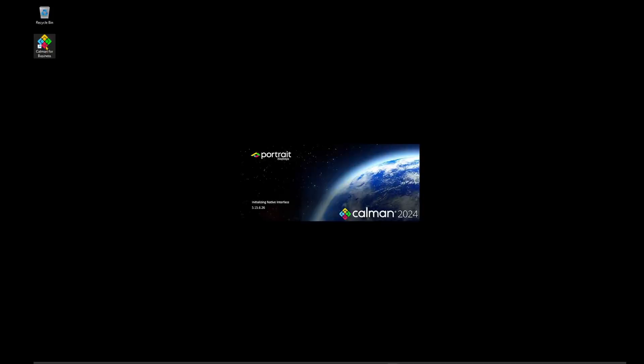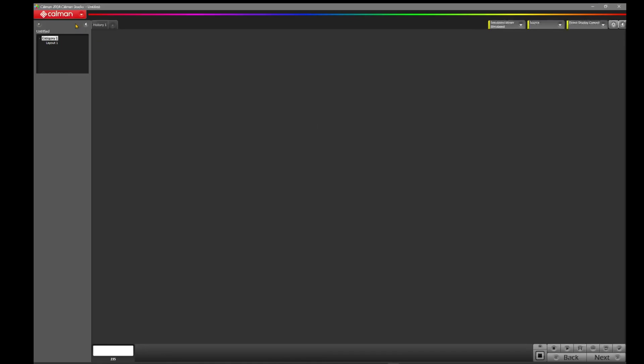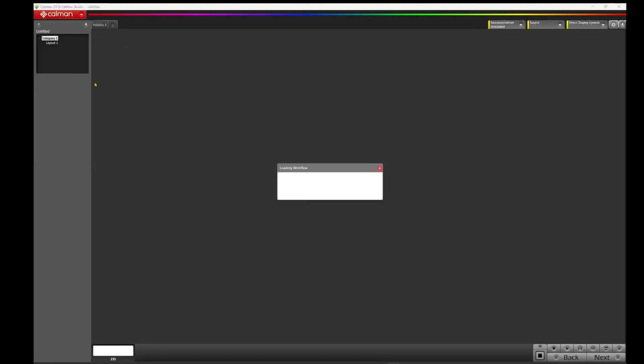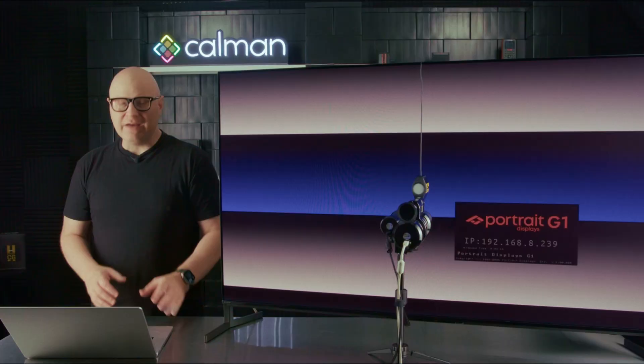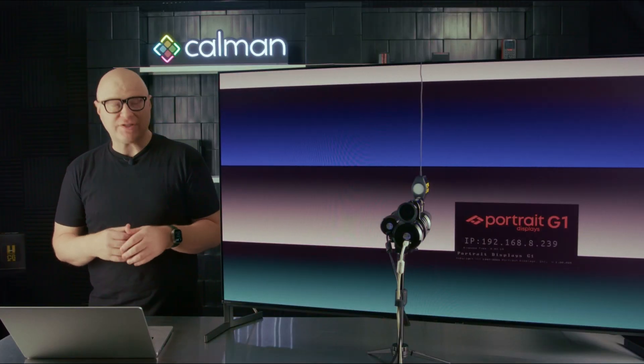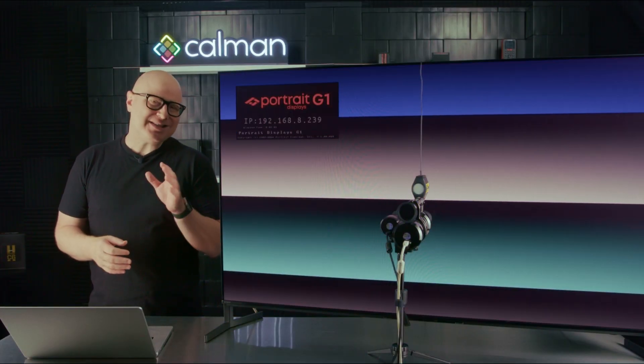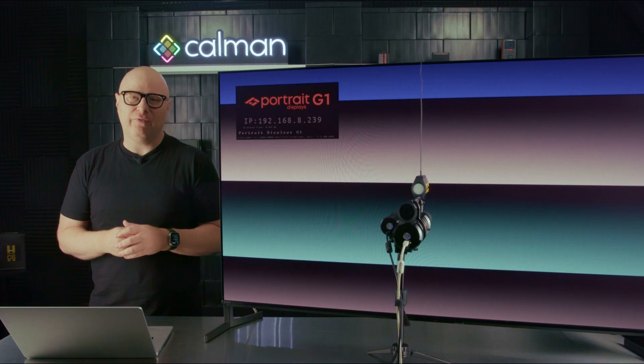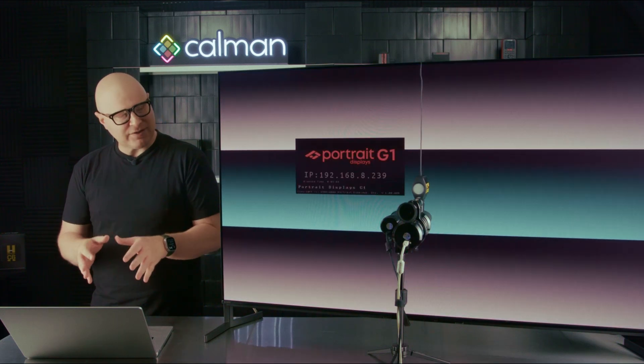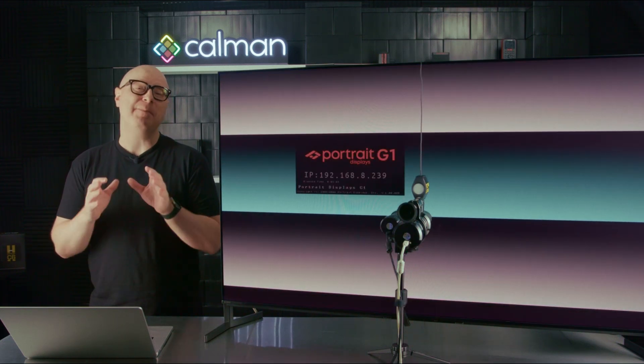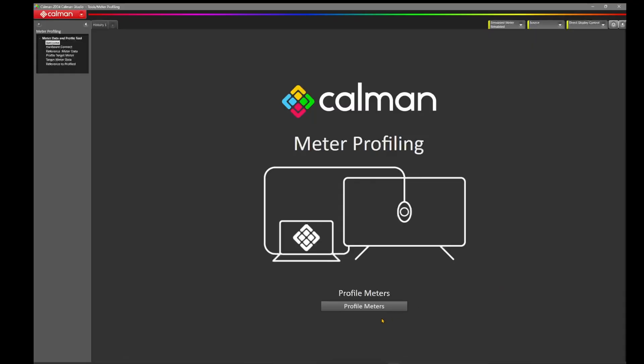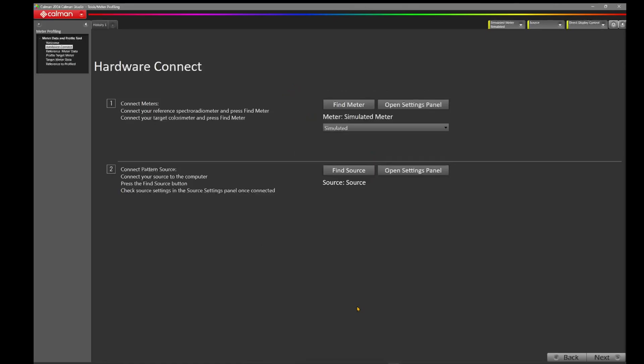Let's get started. I'm going to launch Calman on my computer. We're using Calman Studio. With Calman launched, I'm going to come up to the left corner here, click on the Calman icon, come over to Open Workflow Template, hover down to Tools, and choose Meter Profiling. This is going to open up a workflow that allows us to create a meter profile. But instead of creating a meter profile, I'm going to use this workflow to compare my meter profile. Let's click on Profile Meters. At this stage, Calman would like you to connect to your hardware.